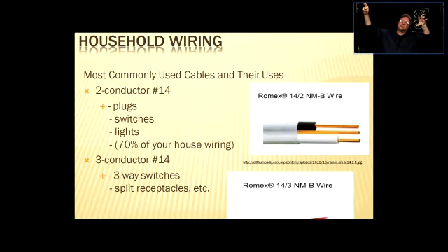Sometimes also the gauge is being upped, or the wire that's used is thicker wire to provide more amperes, to increase the ampacity. Also, when you have cables or branches, which is the branch going from the circuit breaker to the receptacle, going further and further, if it's longer than 100 feet, then you also should use a bigger gauge, which means a lower gauge number, thicker cable, right? But you're going to talk about that in further classes.